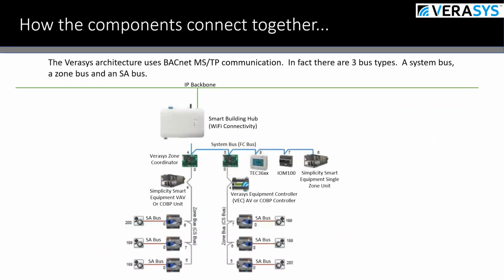So this talks a little bit more about how these components connect together. In this architecture, you have the IP backbone. Of course, this is what's needed to be able to access remotely, and for your email and text. But this system bus here is the BACnet MSTP system. You can have 100 devices on this BACnet MSTP system bus, all daisy chained. However, you notice here, these are the zone coordinators. These are also one of these devices.